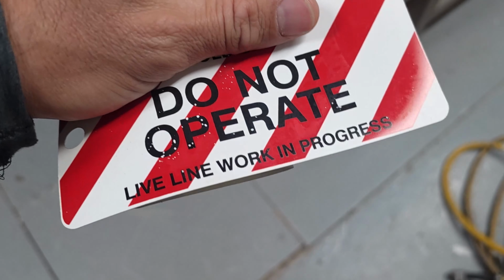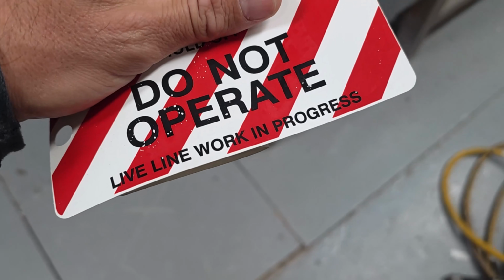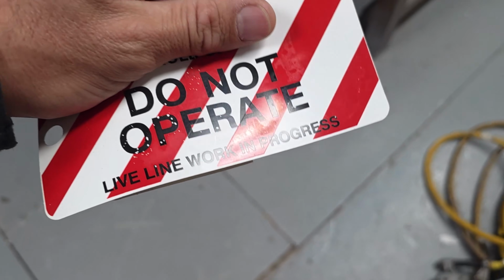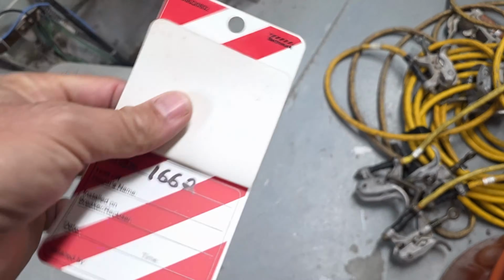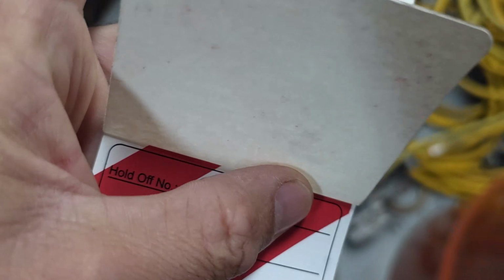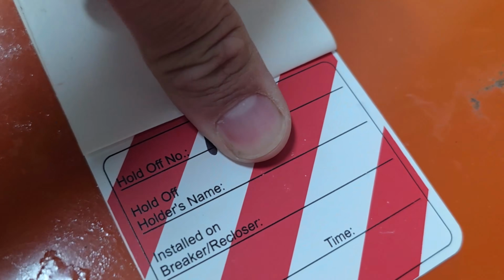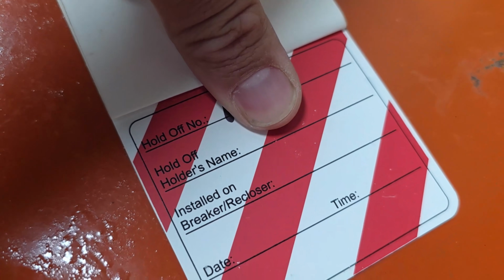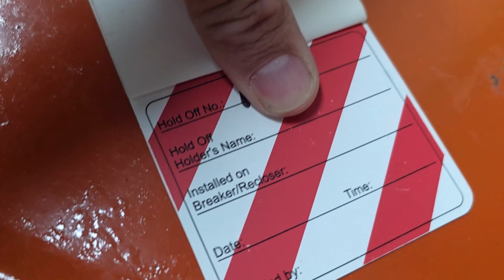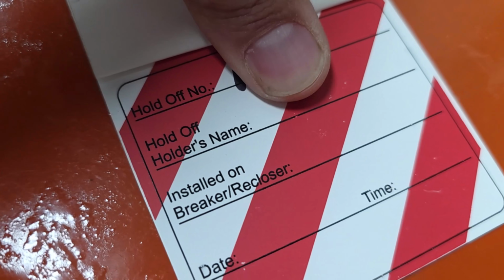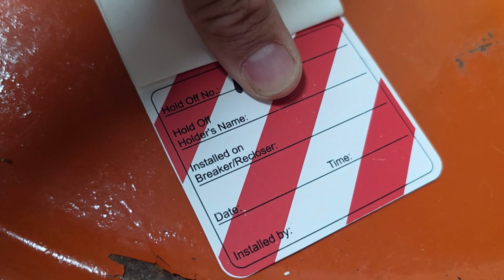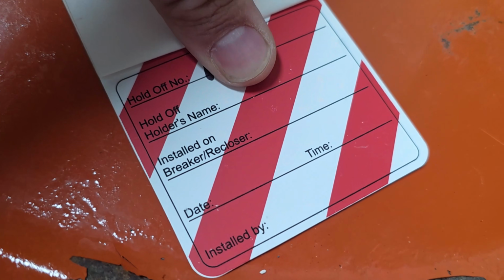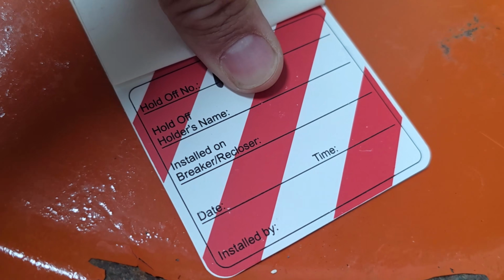When I install the tags, it basically says do not operate, live line work in progress. On our tags we've got a hold off number, so if anyone is in here, they can reference that number with the power system operator and find out exactly what's going on with the lines. The hold off holder's name won't be mine, it's going to be the crew working on the line, and they're a long ways from here.